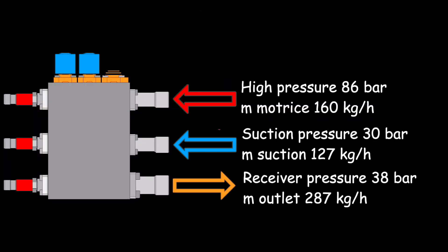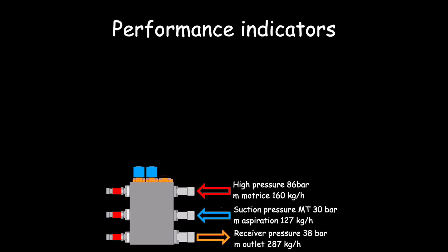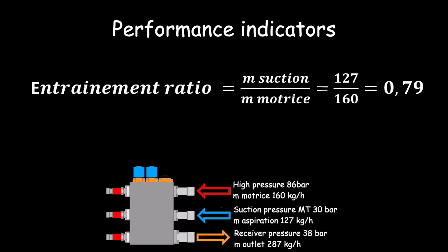The performances of an ejector are represented by two indicators. The entrainment ratio, which is the secondary mass flow lifted divided by the primary mass flow used as motive force. In our example, the ejector lifts 127 kg per hour for 160 kg per hour of primary mass flow, which means an entrainment ratio of 0.79.